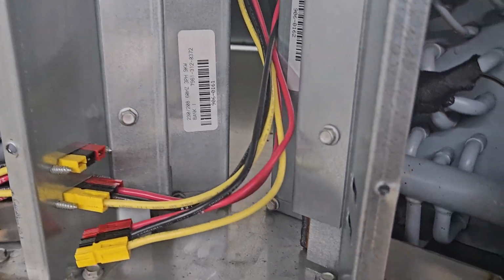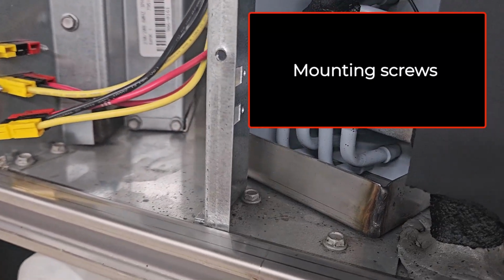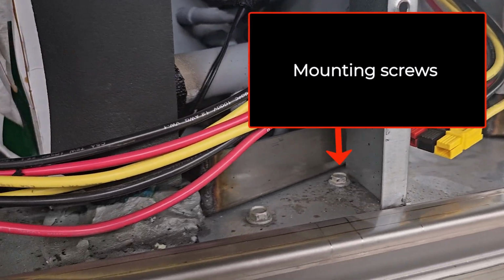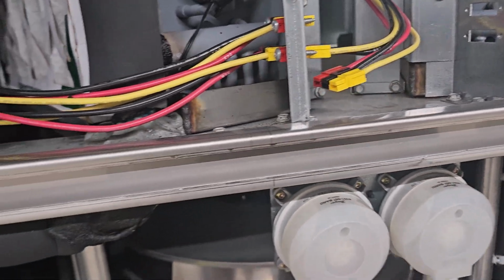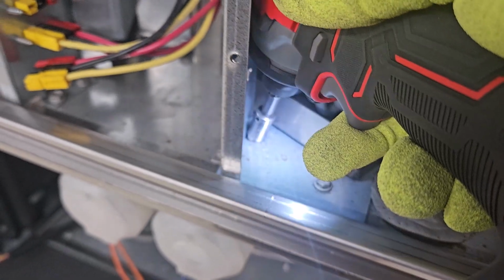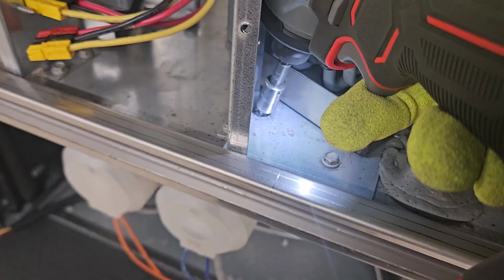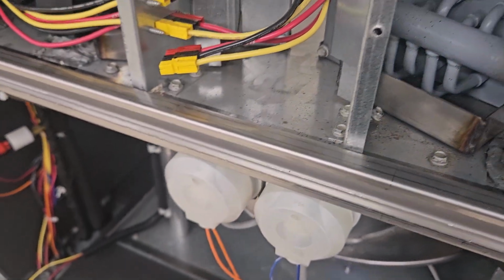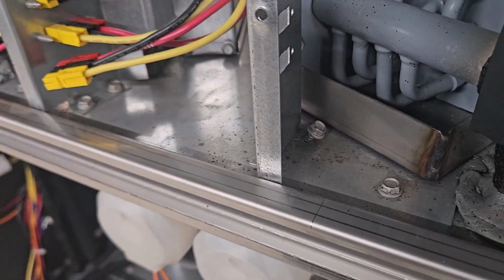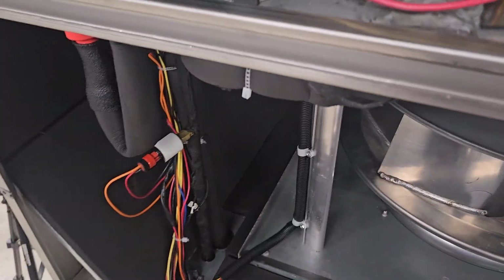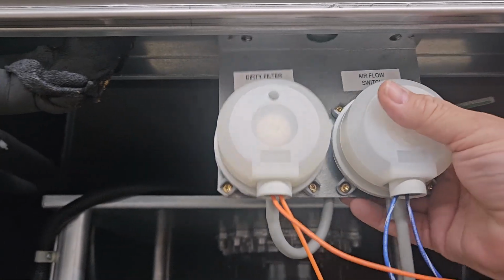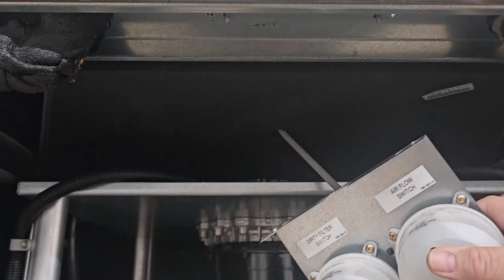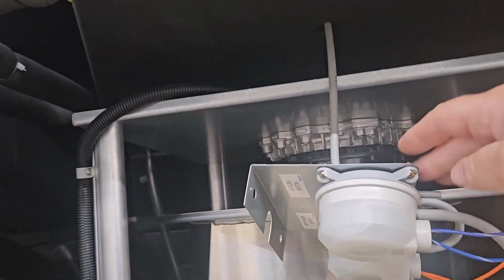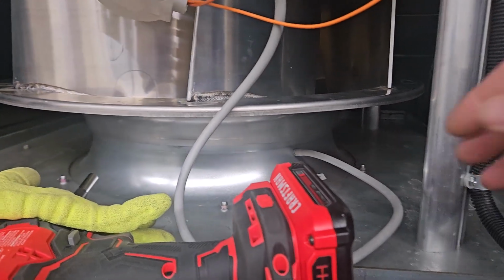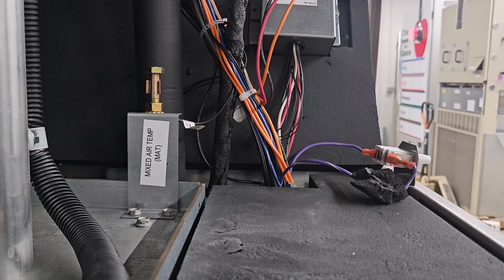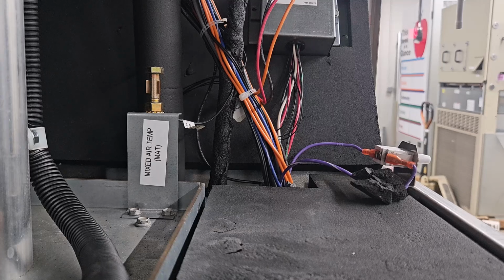These switches may have mounting screws in the indoor blower compartment or may have mounting screws in the filter and evaporator section. If the switches have mounting screws in the upper filter and evaporator section, it would be nice to have a flexible extension to remove the screws. Otherwise, we would have to remove the electrical heating wires to get to the mounting screws. Take a picture of the hoses and remove the hoses attached to the switches and the blower housing.